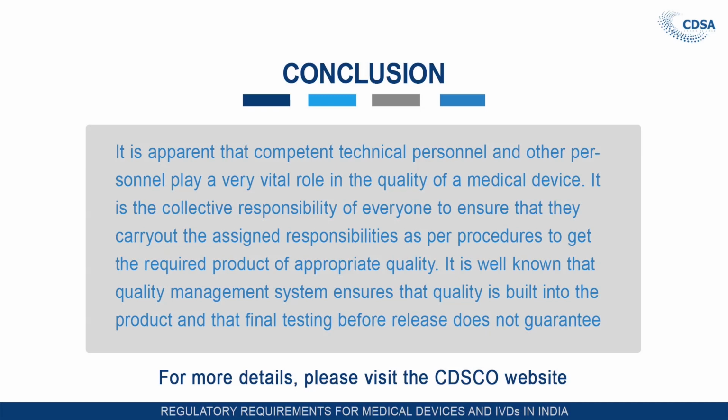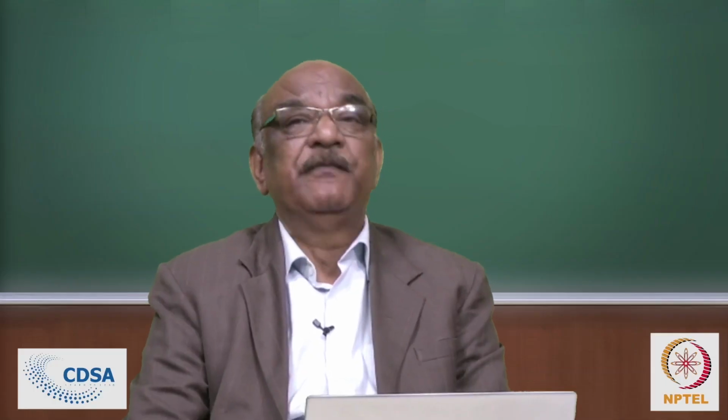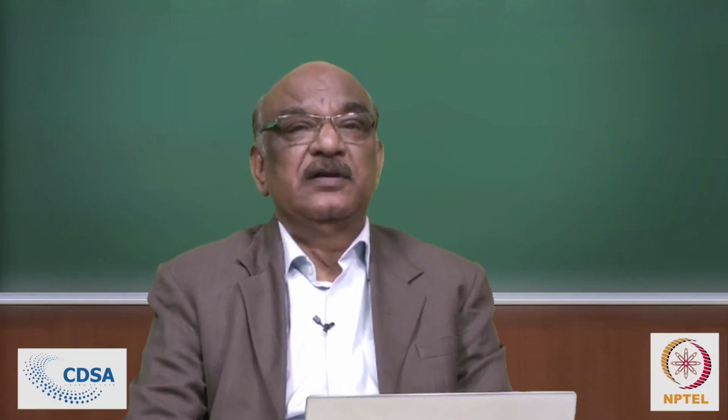What it means in a nutshell is that you cannot test a medical device. Some medical devices can be tested destructively, but most can't. Like a drug, where a sample is taken from the final lot and destructively tested, it doesn't affect the final quality of the product, but you can get a general idea of the quality of the product from that destructive testing. In case of medical devices, a product cannot be destructively tested.